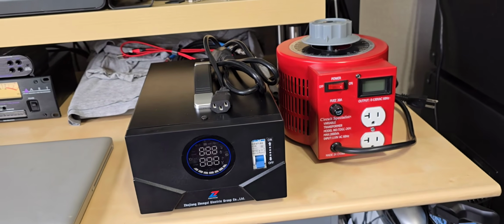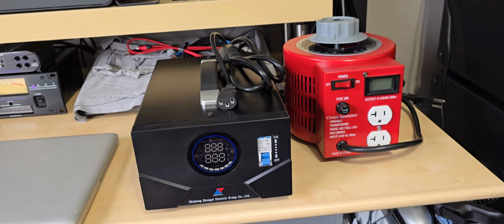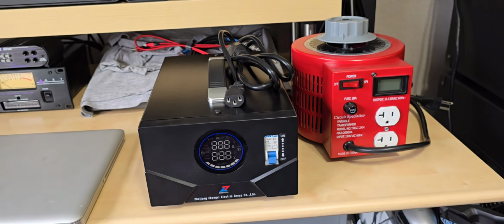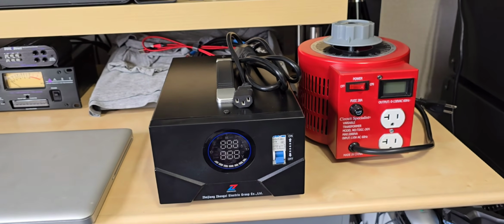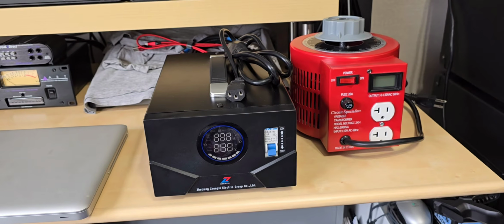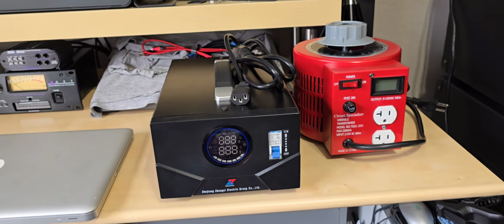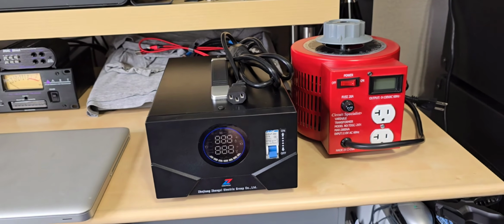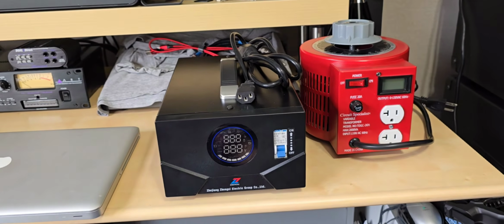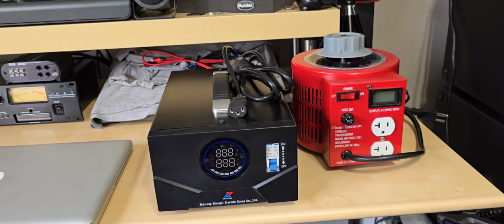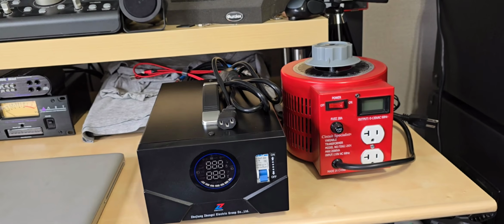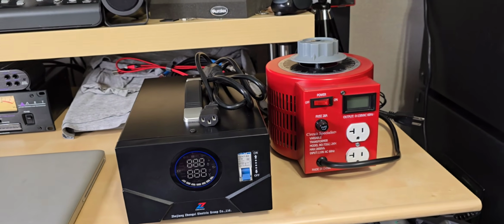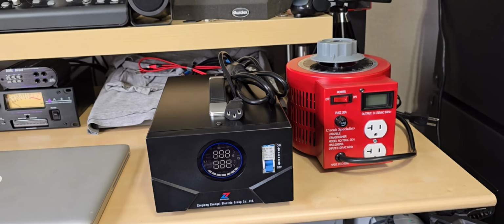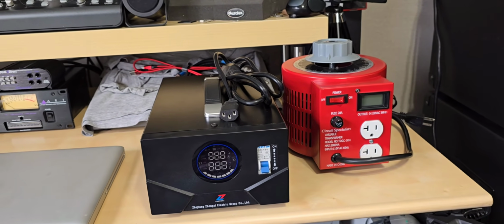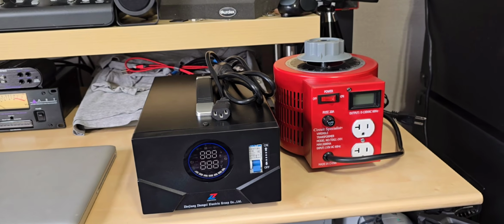An inductor or transformer stores energy in its magnetic field. The slower the frequency, the larger the relative size of those inductor components needs to be in order to suppress those lower frequencies, to correct and suppress total harmonic distortion. We're talking about devices called load and line reactors, very large inductors that are extremely heavy, extremely expensive, and that just is not practical at the portable generator level.